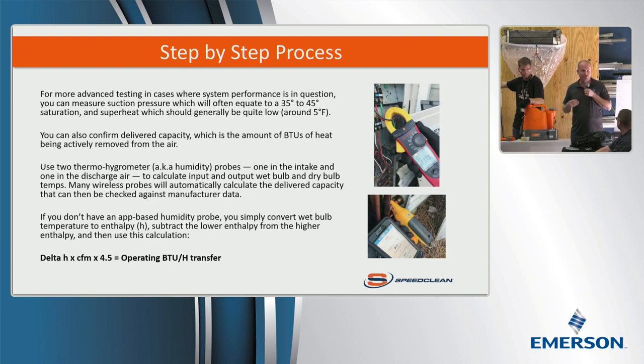So the point being that when you're using MeasureQuick and you profile it, and you say it's a 12,000 or 15,000 BTU ductless system, and then you've looked at that chart from the manufacturer and it says 400 CFM at high speed, you can plug that into the equation as your airflow, then use your two psychrometers, and it's going to tell you what BTUs it's producing.